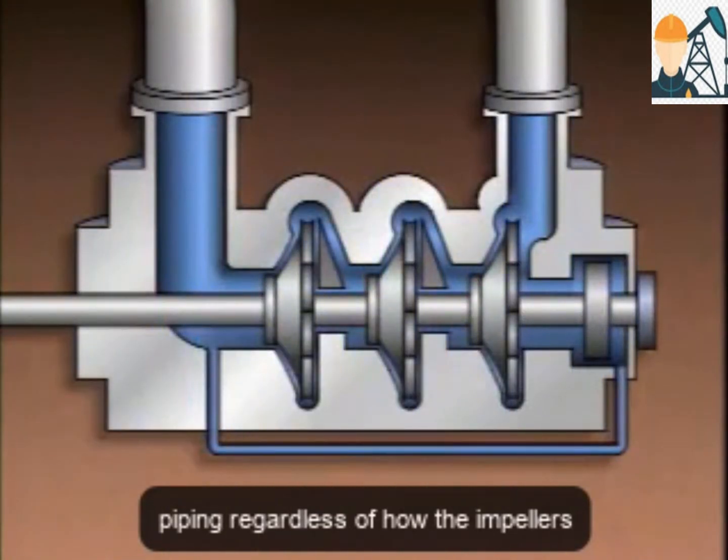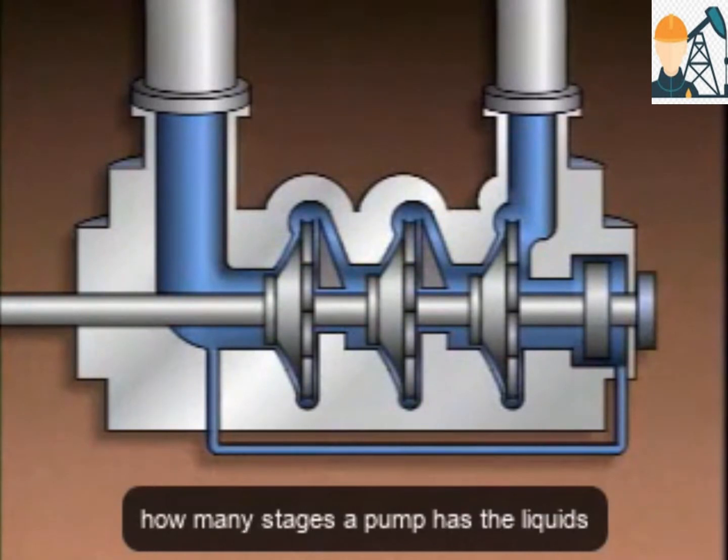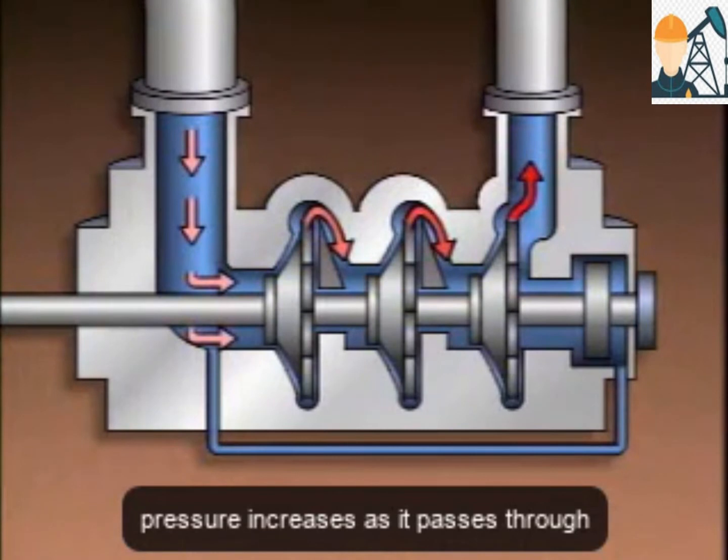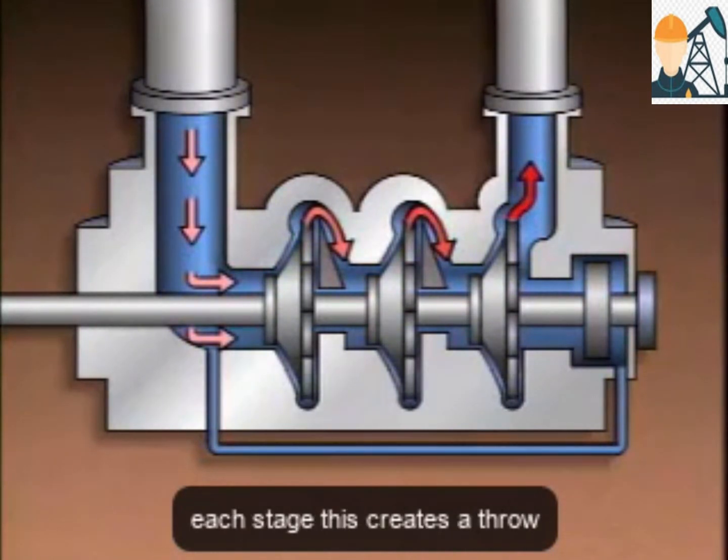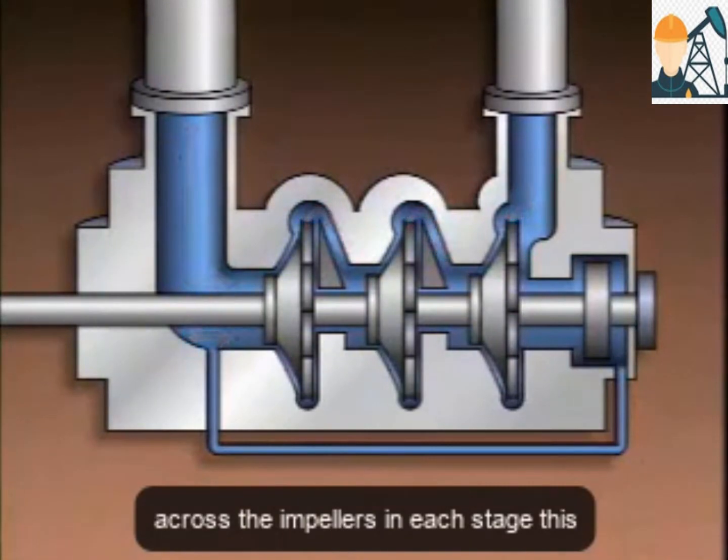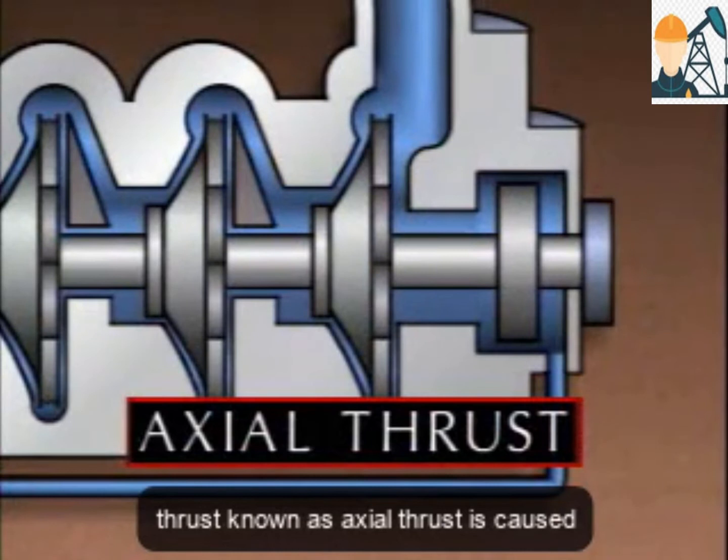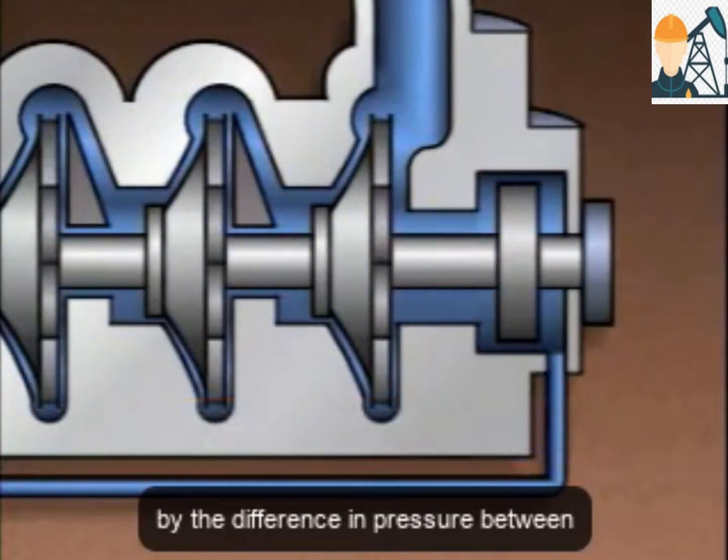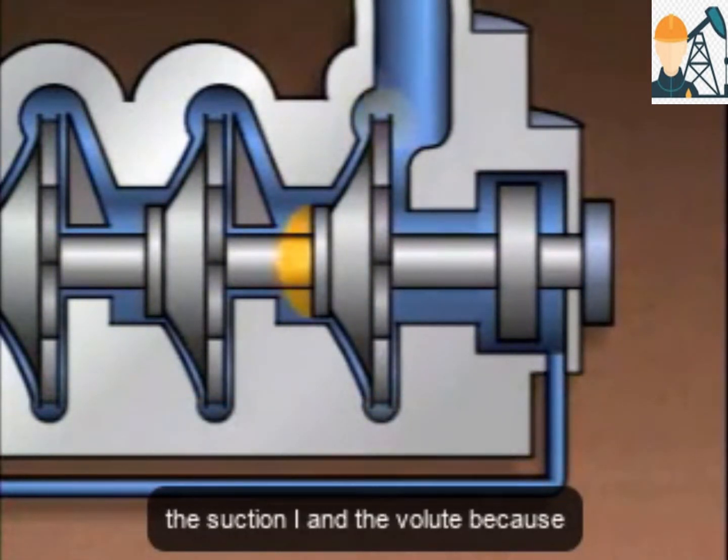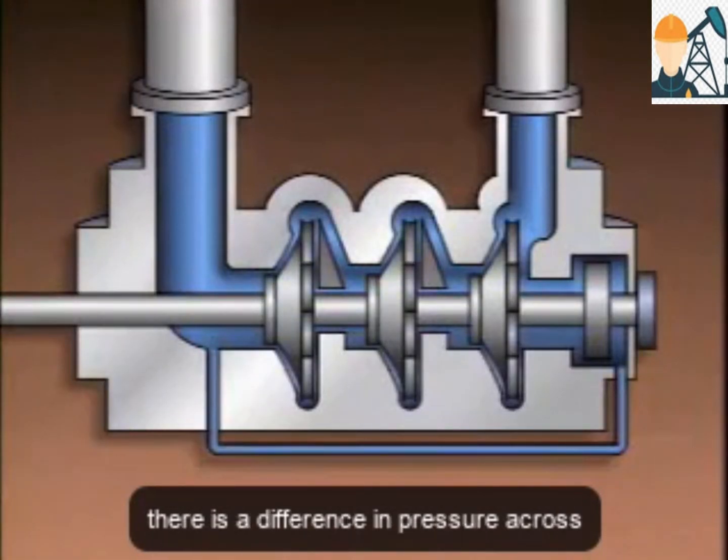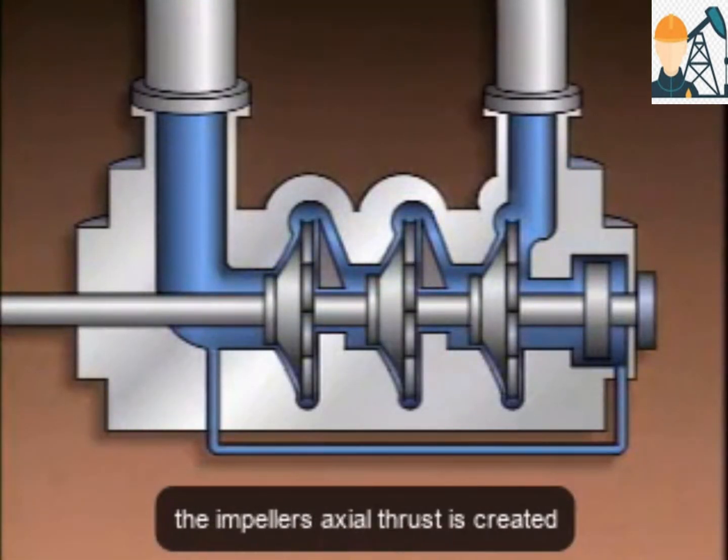Regardless of how the impellers on a centrifugal pump are arranged, or how many stages a pump has, the liquid's pressure increases as it passes through each stage. This creates a thrust across the impellers in each stage. This thrust, known as axial thrust, is caused by the difference in pressure between the suction eye and the volute. Because there is a difference in pressure across the impellers, axial thrust is created.